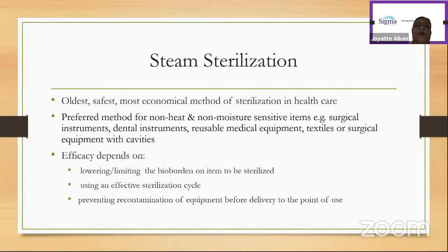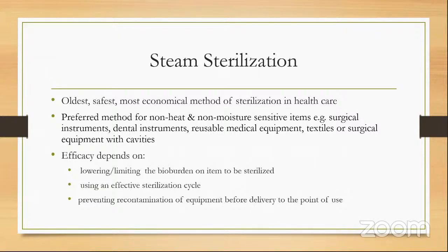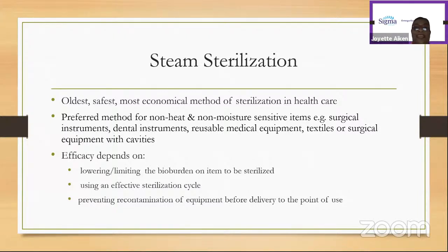So let us talk about steam sterilization. I'm not going to go into a lot of detail about the process, because I think that is too much technical information. But generally, most of us would know that steam sterilization is the oldest, the safest, and the most economical method of sterilization in healthcare. It's the preferred method for non-heat and non-moisture sensitive items like surgical instruments, dental instruments, reusable medical equipment, textiles, or surgical equipment, especially those that have cavities or lumens.